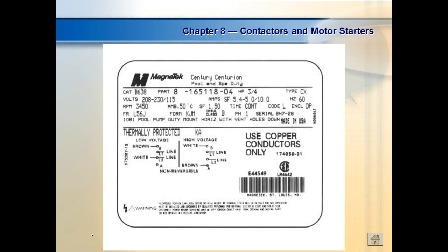What's plugging? You plug a motor and you don't know what plugging is. Y'all know what a jog motor is? Running short bursts, yeah. What's plugging a motor? Everybody in here probably did, especially with a ceiling fan. Plugging a motor is when you reverse a motor without letting it come to a complete stop. You spin it and pull the chain and it reverses automatically, and you hear that thing humming because it's pulling full load current. So we call that plugging motors.